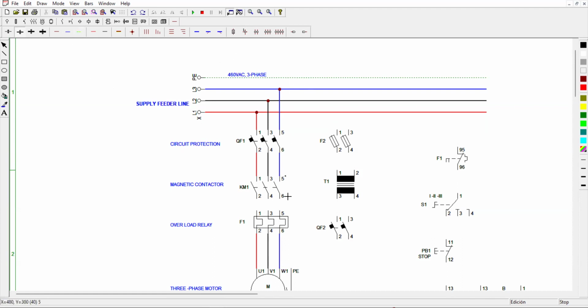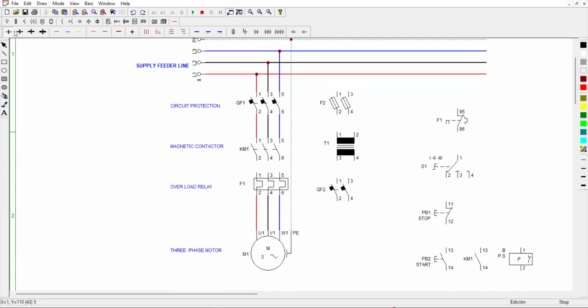Don't forget to connect our equipment grounding conductor of our motor. Let me just erase this one. This will be our equipment grounding conductor. I prefer to use this one like this. Connecting contactor, overload relay, and we will connect our control circuit. This will be our control circuit diagram. This is our supply. Where the blue one.